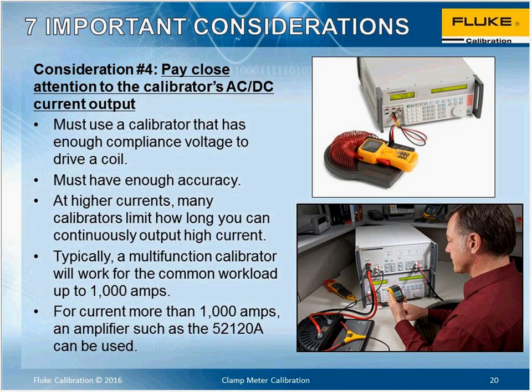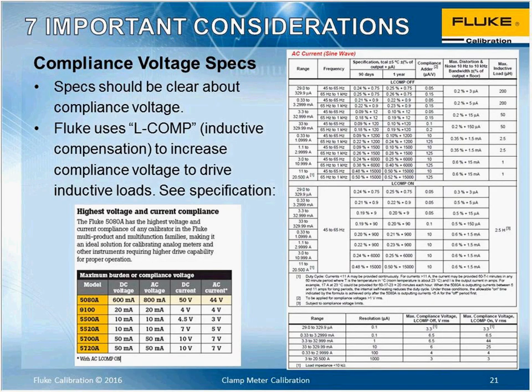So when evaluating these products, you want to make sure of a couple things. One, that it can drive a coil, because most products that you would be using can drive a coil, but also it's a value add if your product can drive a coil, so you can do current clamps if you need to. Products use a function called L-comp, which is inductive compensation. And this basically increases the compliance voltage to drive inductive loads. So in a specification, and a couple of the calibrators in the market also use something similar, you would want to make sure that you look at it in two different ways.